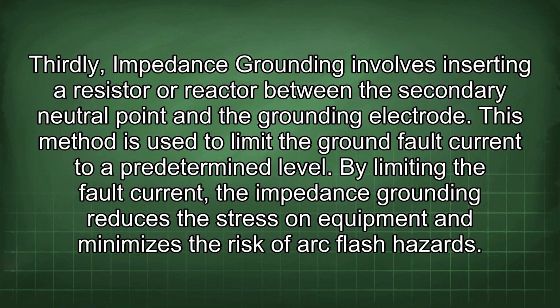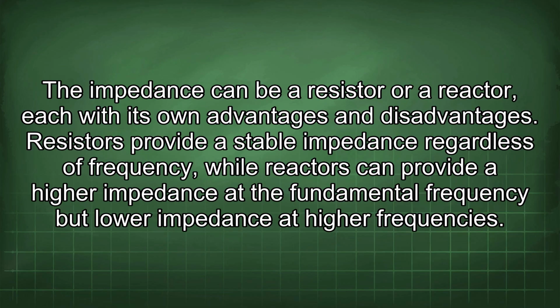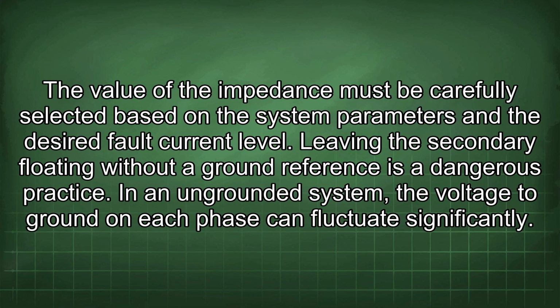Thirdly, impedance grounding involves inserting a resistor or reactor between the secondary neutral point and the grounding electrode. This method is used to limit the ground fault current to a predetermined level. By limiting the fault current, the impedance grounding reduces the stress on equipment and minimizes the risk of arc flash hazards. The impedance can be a resistor or a reactor, each with its own advantages and disadvantages. Resistors provide a stable impedance regardless of frequency, while reactors can provide a higher impedance at the fundamental frequency but lower impedance at higher frequencies. The value of the impedance must be carefully selected based on the system parameters and the desired fault current level.